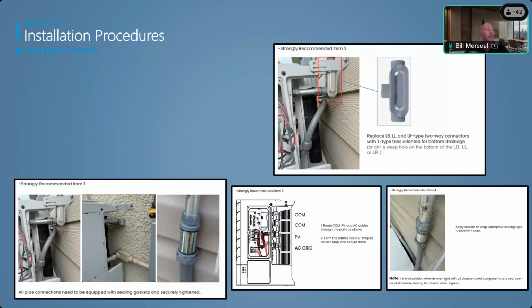So what we've done to help: one, be aware—try not to install these underneath a water spout. If you're doing it underneath the gutter, make sure the gutter is not pouring onto the battery. I've had two situations where they installed it where the gutter didn't go all the way down, so it just had a hole, and it was literally right above the battery. These are NEMA 4X rated, so from external exposure they are rated to have water on them, but again, it's not the best idea to put them there. If you can help it, try to refrain from just putting things underneath water spouts.